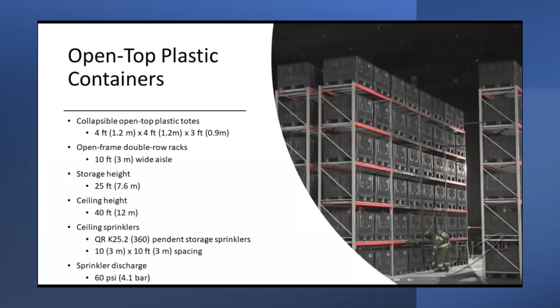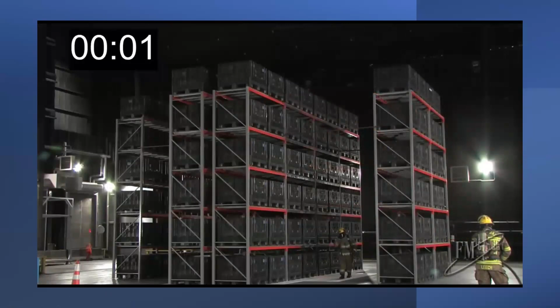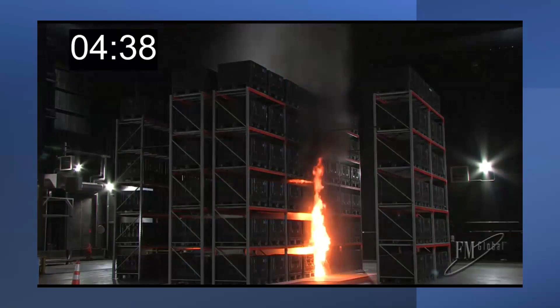The same 195 gallons per minute or 740 liters per minute per sprinkler. At time 0, the igniters are lit. At 4 minutes and 25 seconds, flames can be seen above the top storage level, and at 4 minutes and 30 seconds, the flames are almost up to the ceiling level. At 4 minutes and 35 seconds, the first sprinkler operates, and the flames are quickly driven down the rack to the lower tiers. Fire's being knocked down.